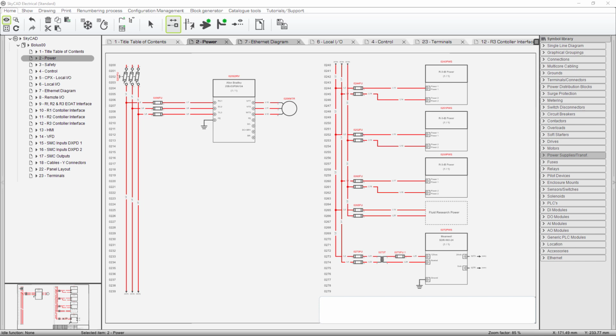Others are 600 volts. So if you've got 480 coming in, you need a 600 volt rating on anything that's got 480 volts on it. You need a 600 volt rating. And then with disconnects and fuse blocks, besides a 600 or 300 volt rating, it's also got a current rating, the maximum amps you can run through each pole. So a 60 amp rating is a larger device than a 30 amp rating. If you have 240 volts, 3-phase for your design, there's no reason to spend the money for a 600 volt rating device that takes up more space and is more expensive.